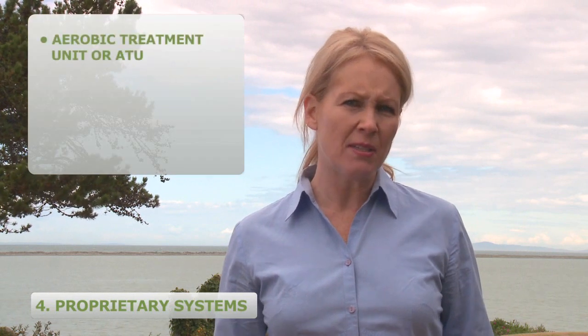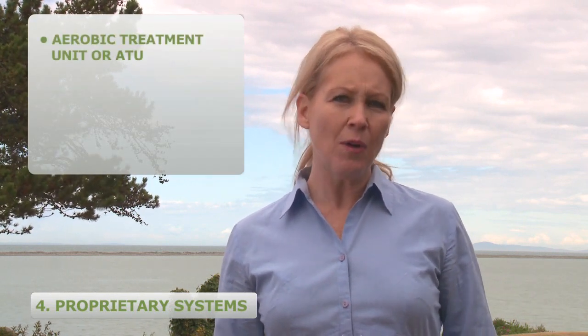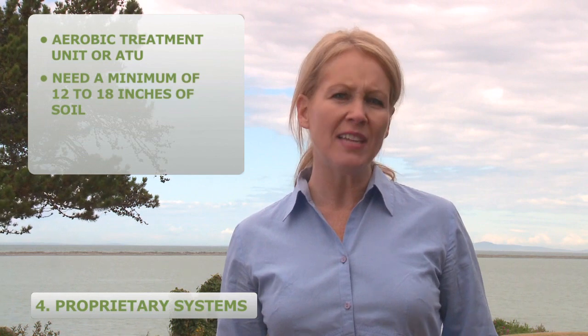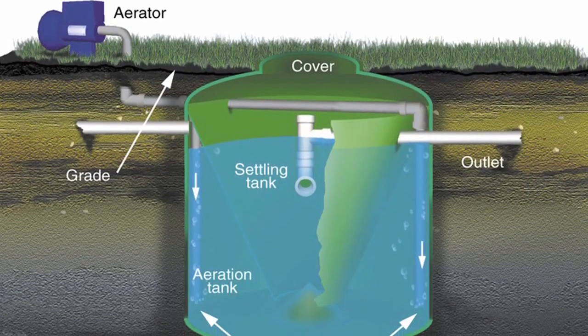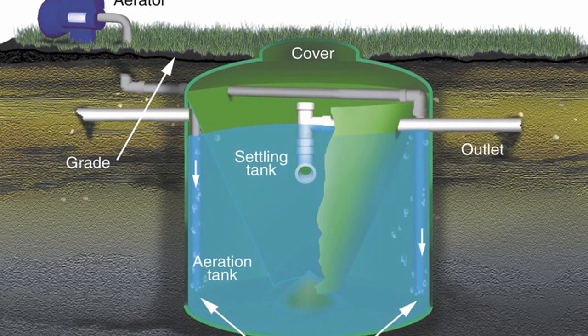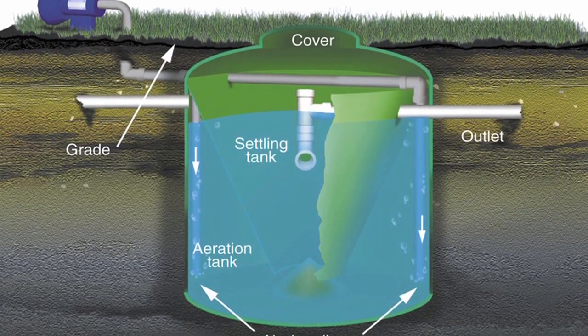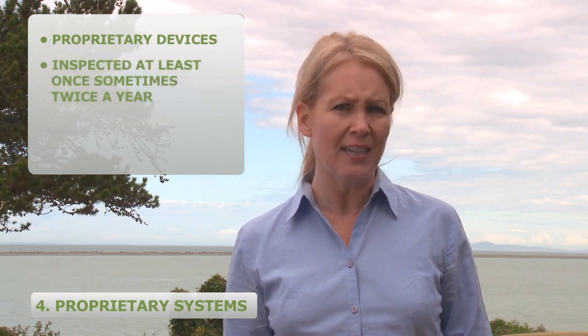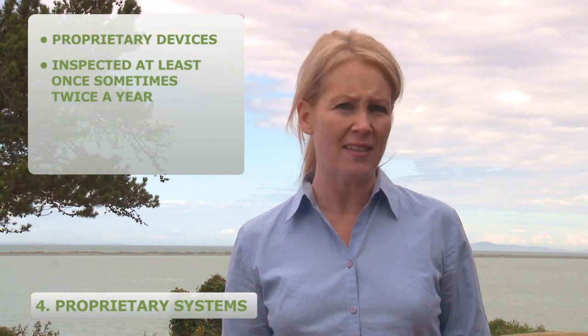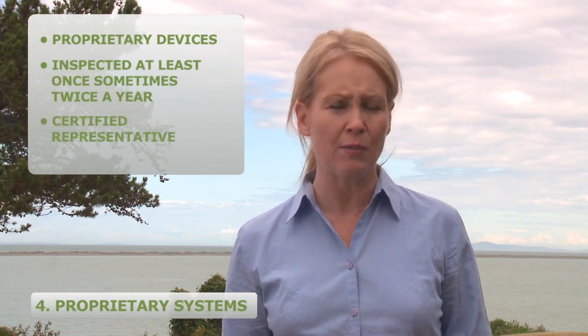There are several proprietary systems for properties that do not have sufficient native soil depth. One type is an aerobic treatment unit, or ATU. Aerobic systems need a minimum of 12 to 18 inches of soil. A blower or aerator injects air into a tank, enhancing the aerobic microbial action. This type of system will often require some form of disinfection such as chlorine or UV treatment before the wastewater enters the drain field. ATUs are proprietary devices and are required by the manufacturer to be inspected at least once, and sometimes twice, a year by a manufacturer's certified representative.